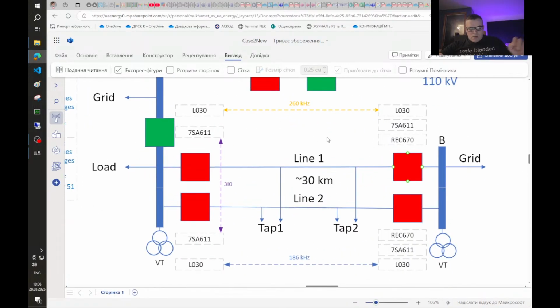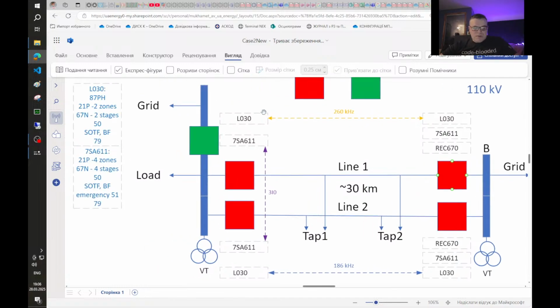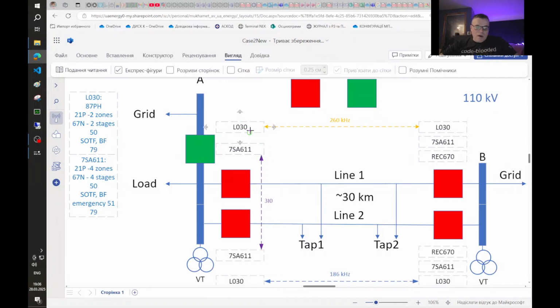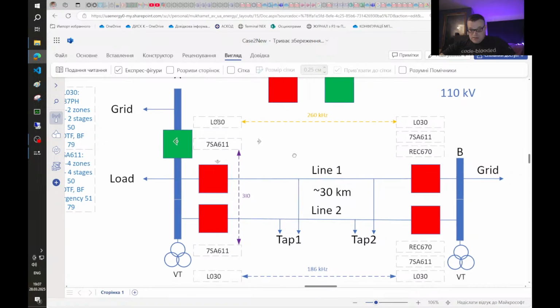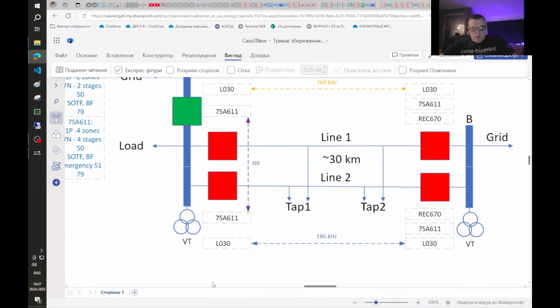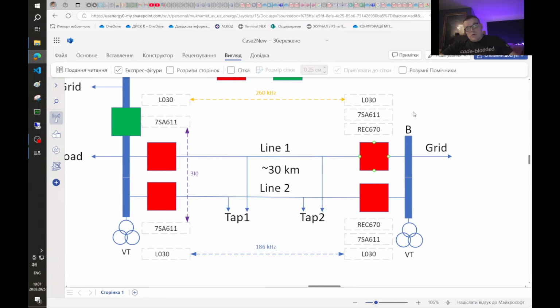So if we talk about protection philosophy, on substation A there are L030. This is the ID from our Ukrainian manufacturer and the well-known 7SA611. On both sides, designers made a connection for mutual coupling, but our settings engineer doesn't use it. On the substation B side, protections are the same, except that there are BC units based on REC 670 from ABB.